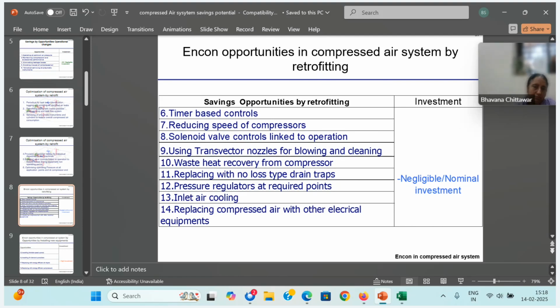Okay. Then replacing with the no loss drain traps. You see, the majority of the customers or clients opt for timer based auto electronic traps. These traps don't know whether moisture is there or not. They will keep on draining at a preset frequency or preset timings. So mostly air will be drained. It's costly air that is getting drained. There you can think of either a no loss type trap, or I will give one more option. I'm coming to that in a presentation separately.